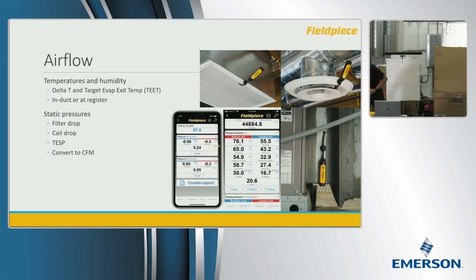Another way that we can check performance of our airflow is measuring static pressures. Okay? Now, sometimes static pressures can be like a hassle to measure. Got to pull out a whole spaghetti ball of tubes, and put them in the right location. But static pressures are very, very useful to take because they measure the amount of restriction to the airflow in your ductwork and across your equipment. So there's a couple different tests that we can take when we're measuring static pressures.